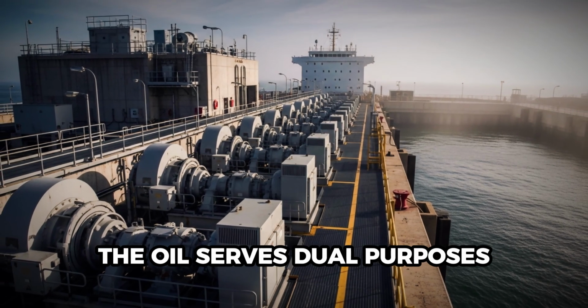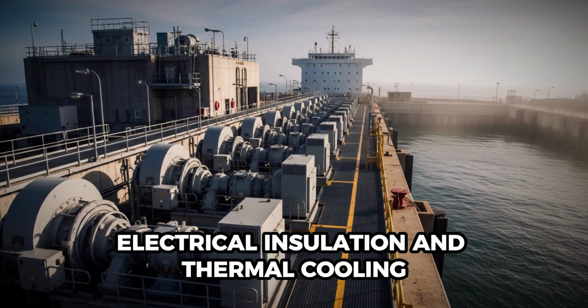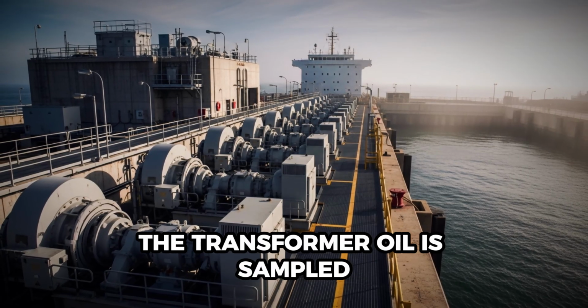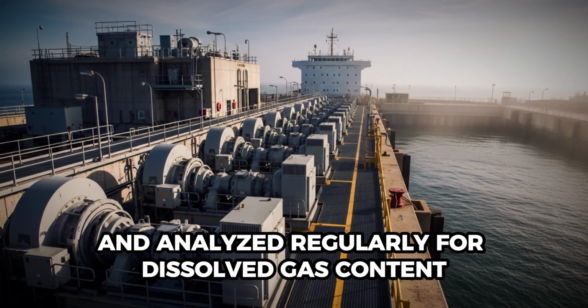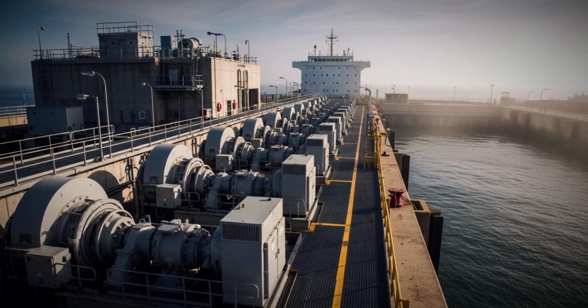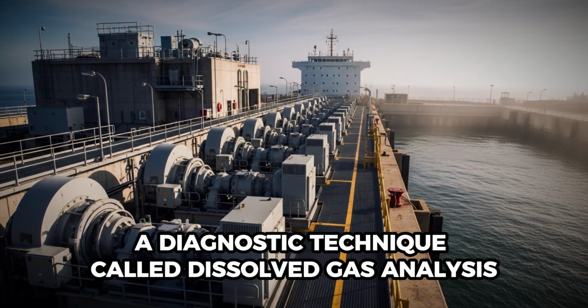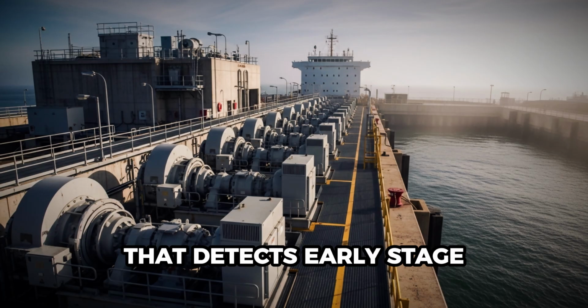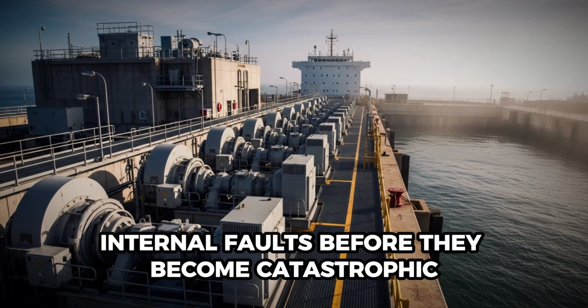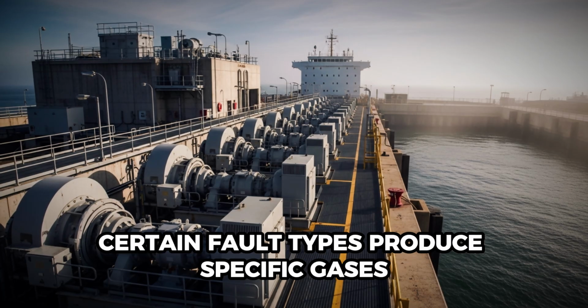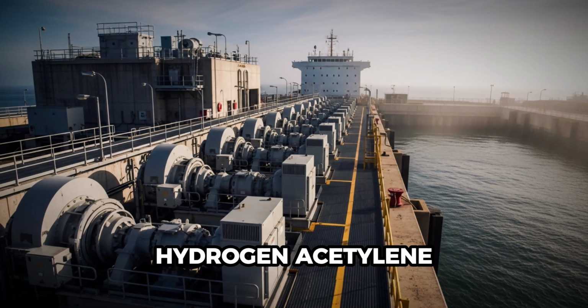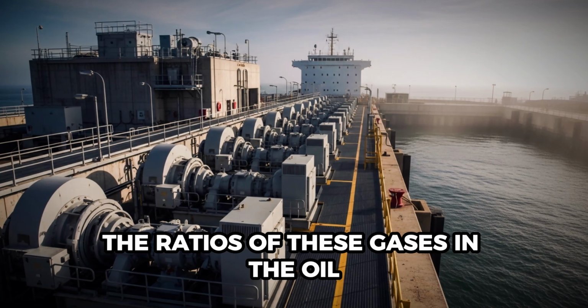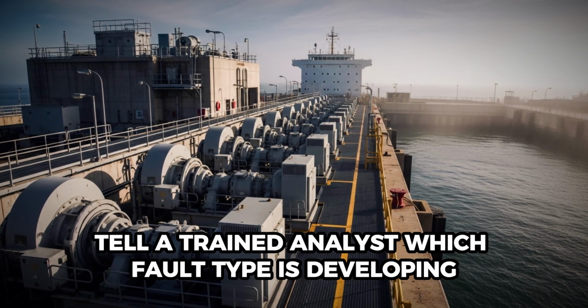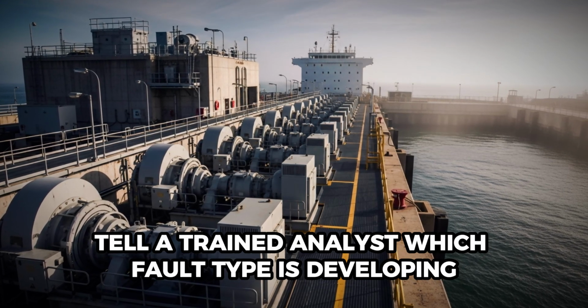The oil serves dual purposes, electrical insulation and thermal cooling. The transformer oil is sampled and analyzed regularly for dissolved gas content, a diagnostic technique called dissolved gas analysis that detects early-stage internal faults before they become catastrophic. Certain fault types produce specific gases, hydrogen, acetylene, and ethylene.